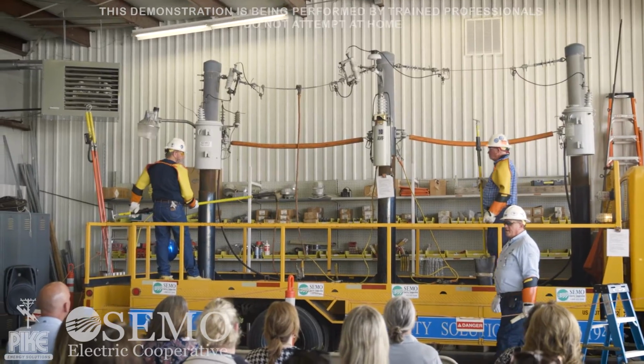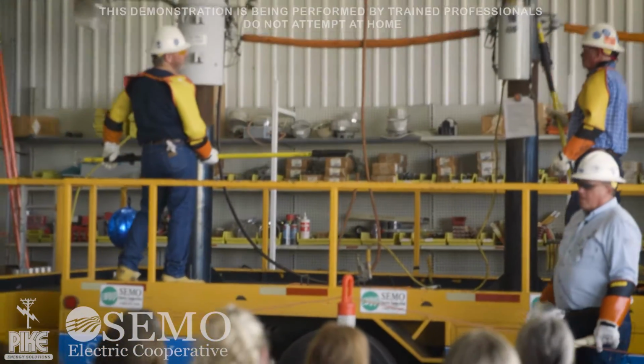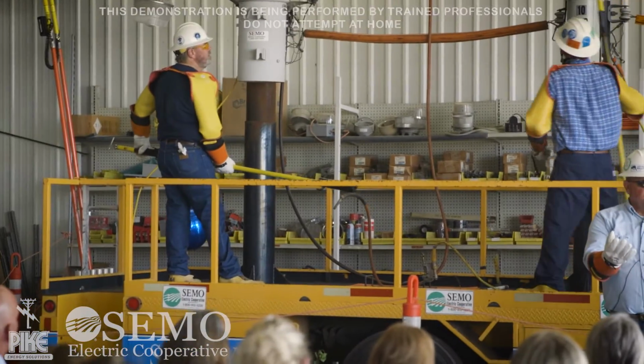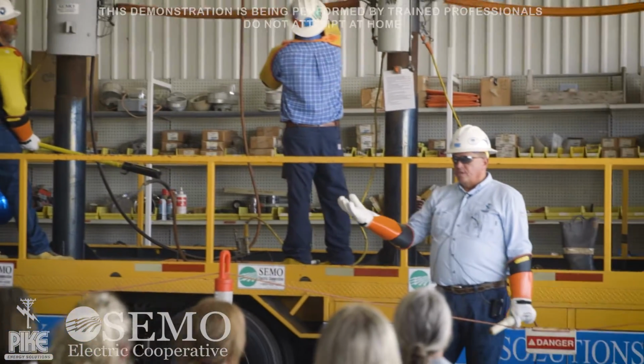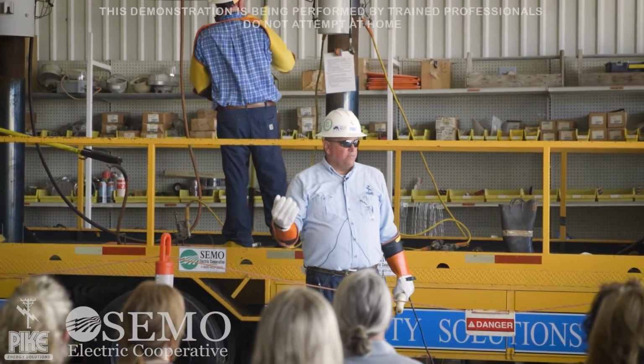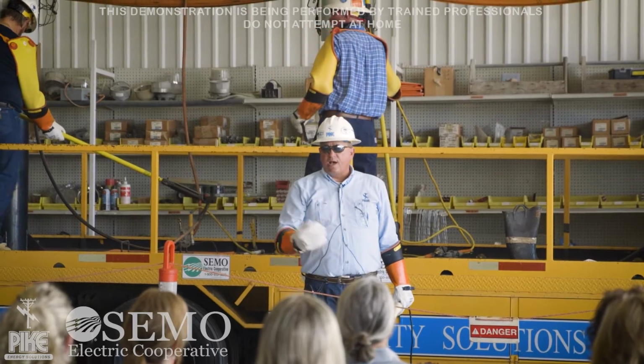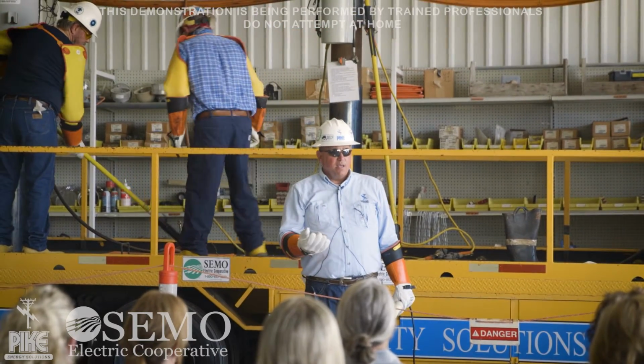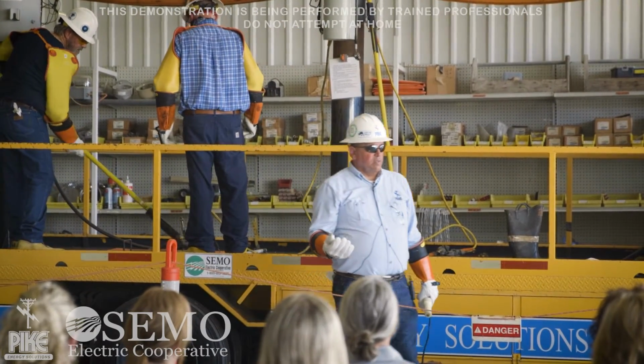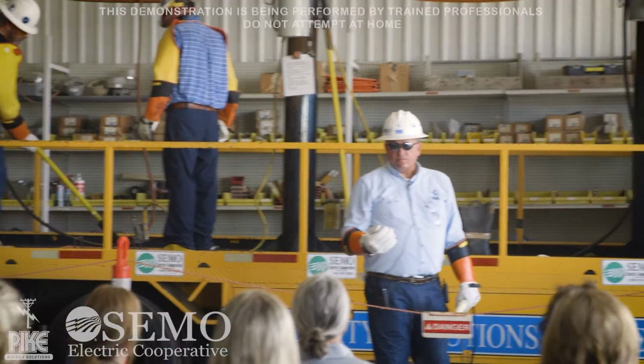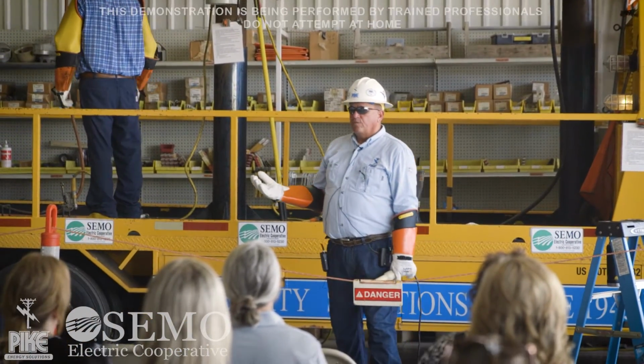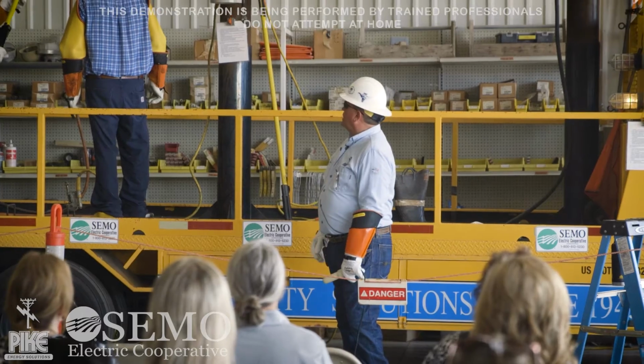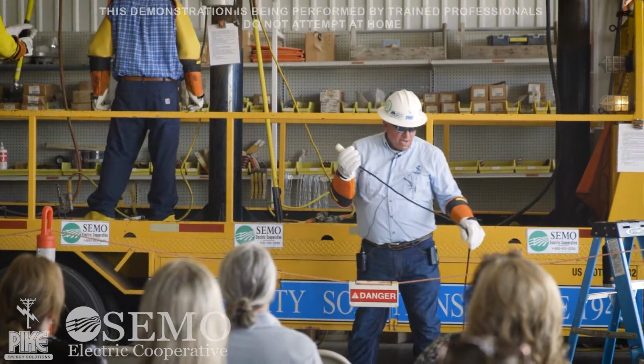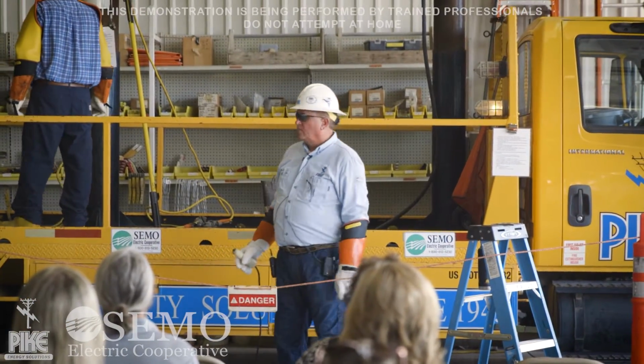We call that a snake in the grass. It's laying there, looks harmless, but that line is still energized. Matter of fact, a power line can fall on the ground and lay in snow and ice, it can lay in sand, it can lay in certain types of soil and still be energized. You don't know that. You always have to make sure that line is de-energized before we touch it.